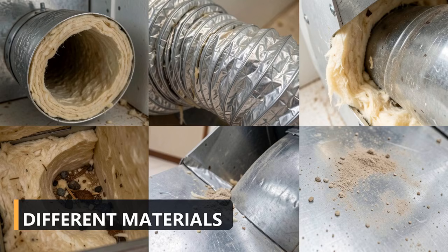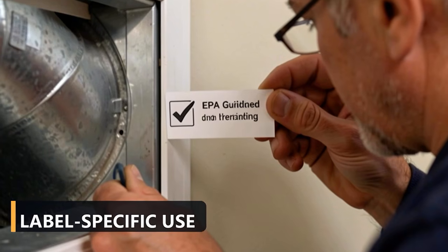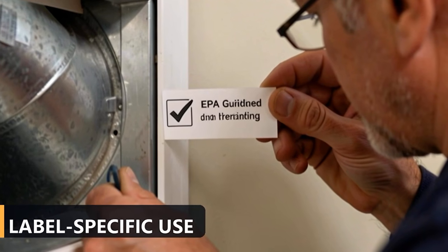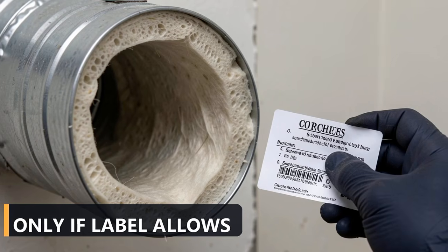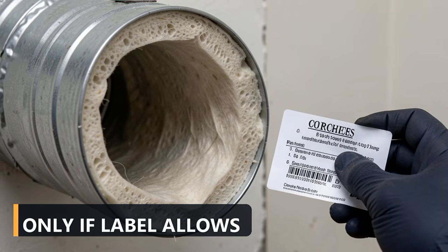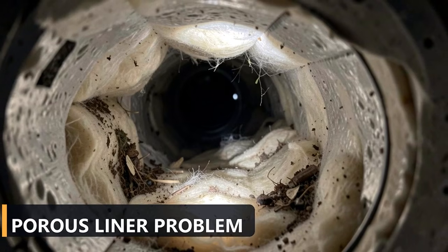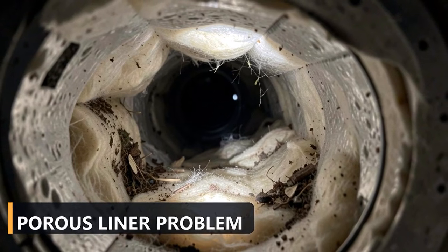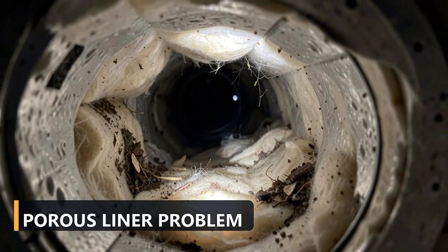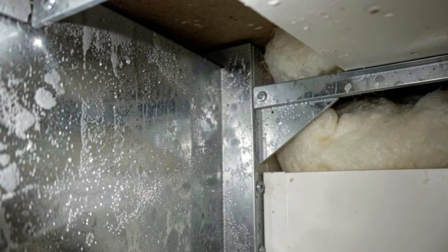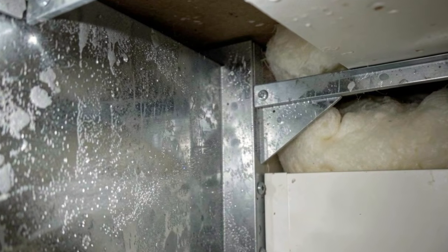The EPA warns that biocides should be used in duct systems only where the product label specifically allows that use. Porous or internally lined ductwork presents a special problem because contaminated insulation may not be effectively cleanable, and indiscriminate spraying can add moisture without removing the source. A fine peroxide mist sent into a return can also be carried toward the filter, blower, coil, and occupied rooms.